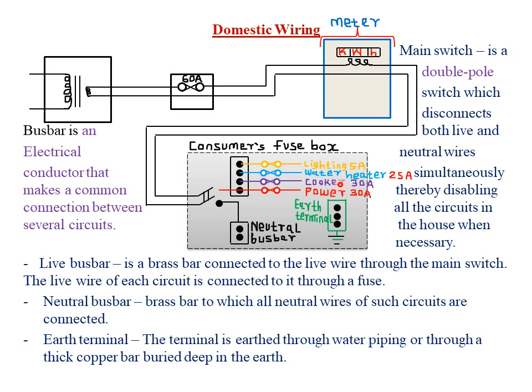The other pole connects to the live wires of the lighting circuit, the water heater, the cooker, and the power circuit. The lighting circuit usually takes a minimal current of about 5 amperes, the water heater takes about 25 amperes, the cooker about 30 amperes, and the power circuit also about 30 amperes.